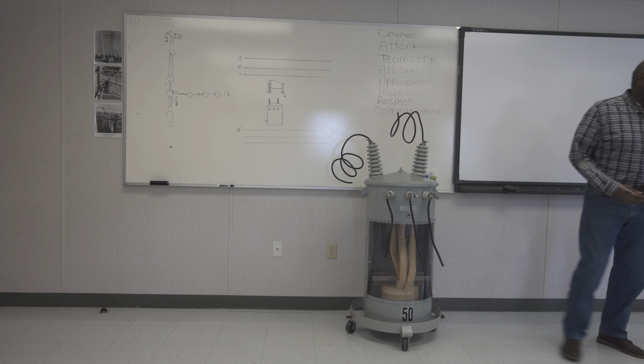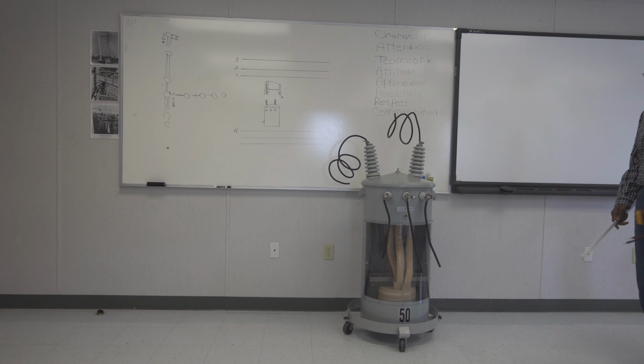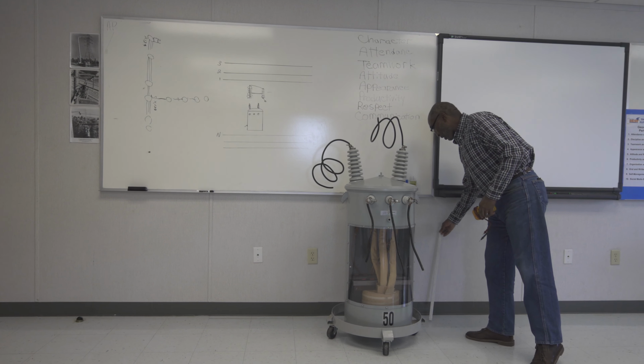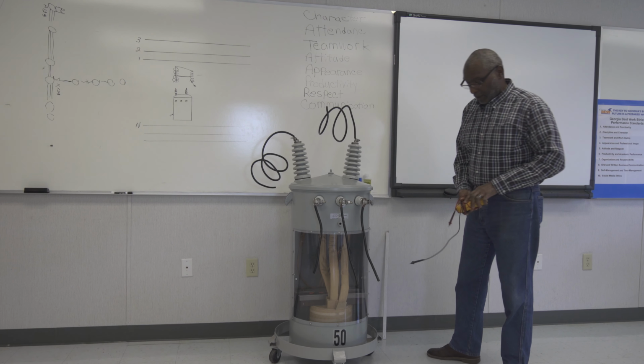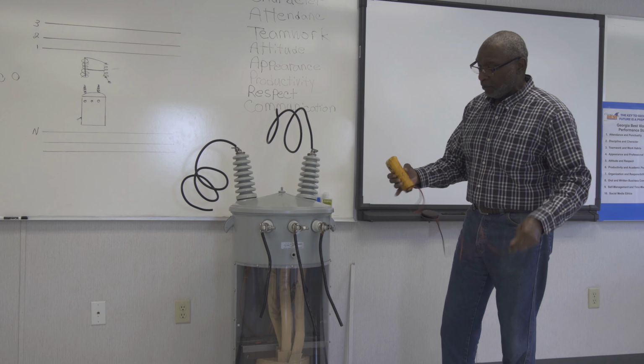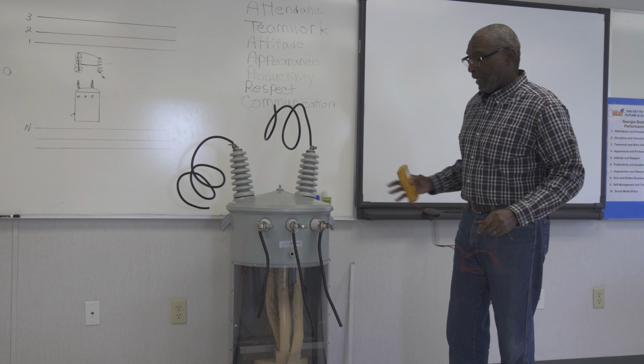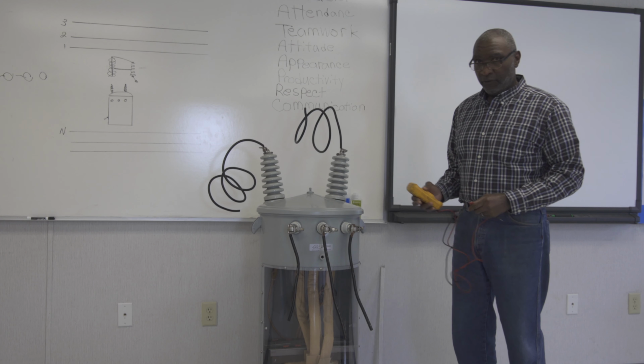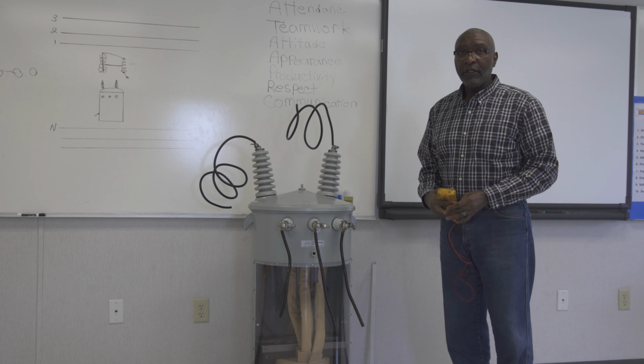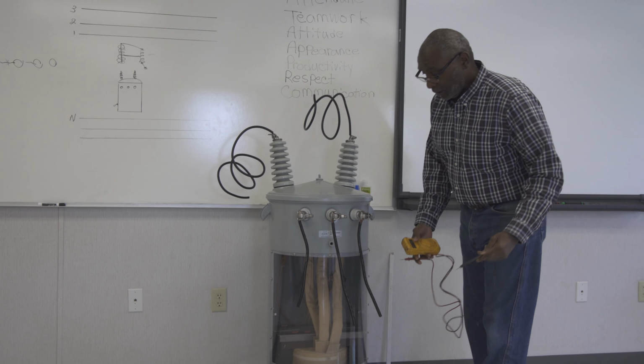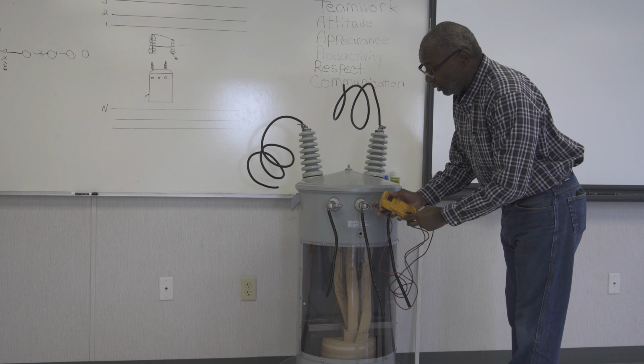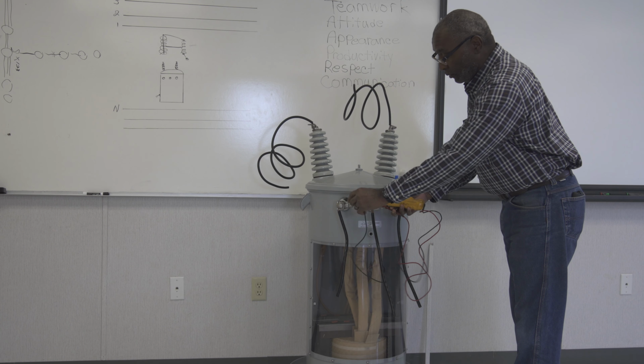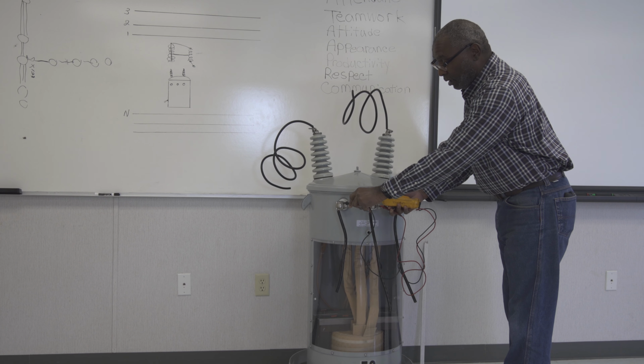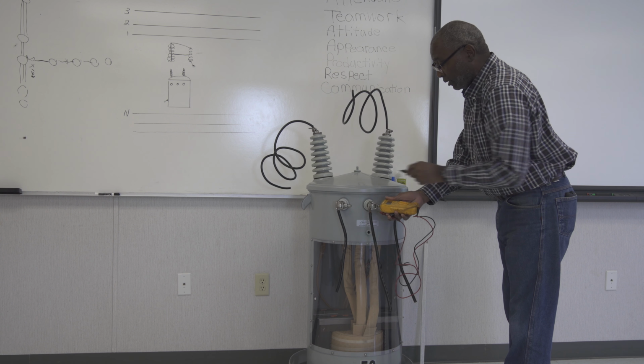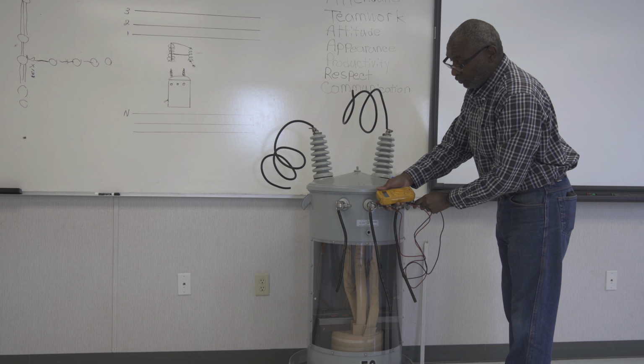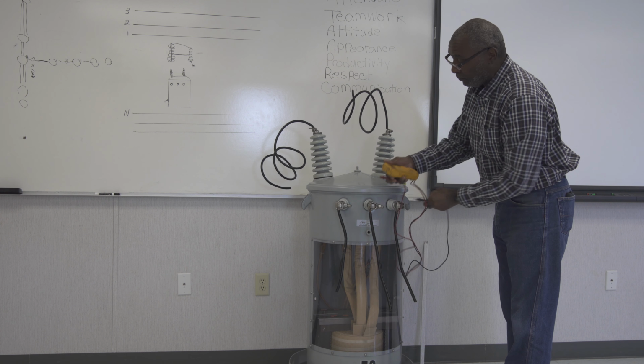And what I want to do is demonstrate using a voltmeter as to what that would look like when you're measuring the voltage. And on your transformer, you're only going to measure voltage on the low side of your transformer. So checking on your leads, right here is the neutral. This is a hot leg, 120, reading on your voltmeter, 120, reading on your voltmeter.